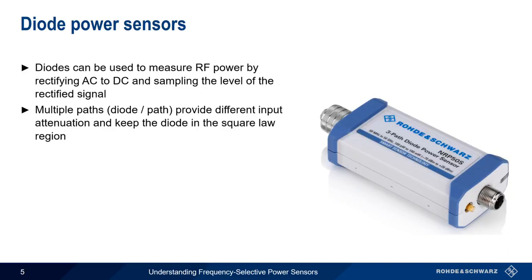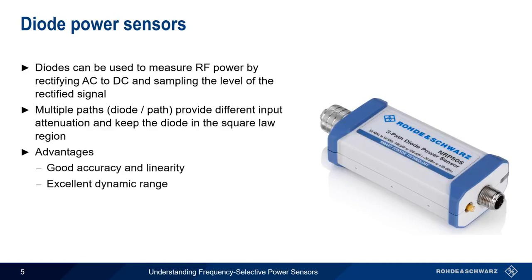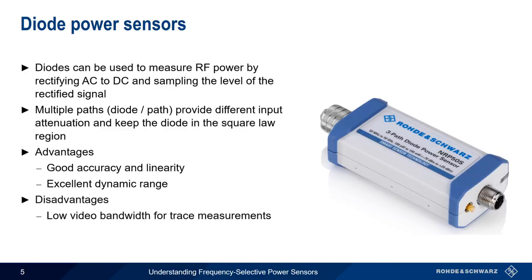Diode-based power sensor advantages include good accuracy and linearity, and an excellent dynamic range, especially when compared to thermal sensors. The main disadvantage of diode sensors is that their low video bandwidth makes trace measurements difficult.